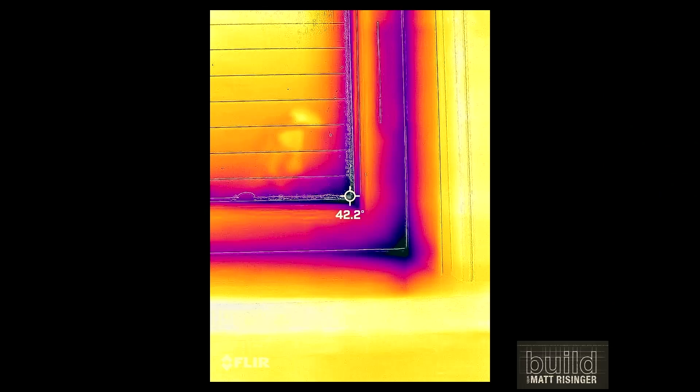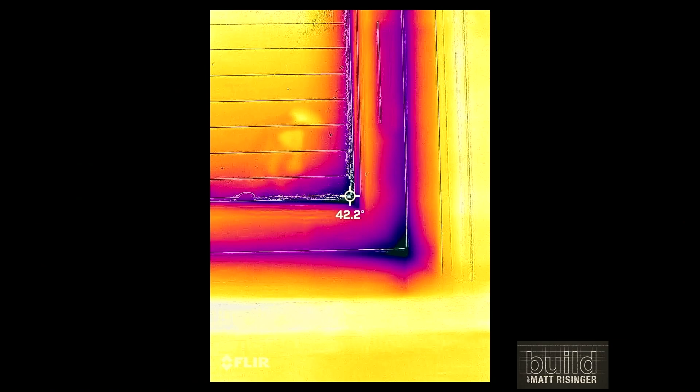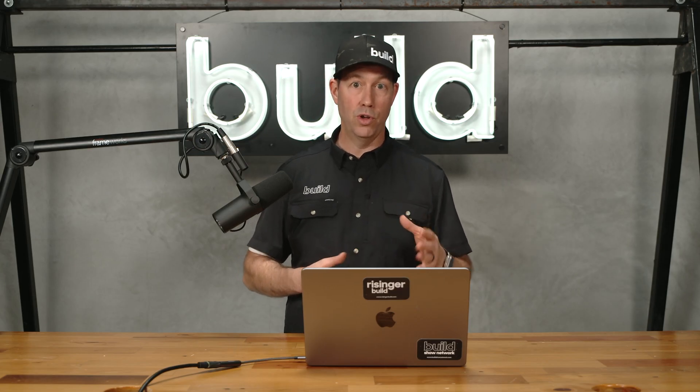Here's that same condensation window viewed through my FLIR thermal gun. You can see the corner of that glass is 42.2 degrees. Remember, that's below the 44-degree dew point under these conditions — which means even a good window that meets code, even a thermally broken composite window, is having condensation issues. It's simply a matter of the window's surface temperature versus the interior dew point.